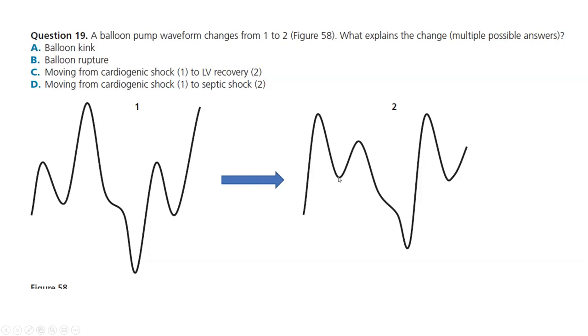Balloon kink and balloon rupture can cause poor augmentation, but they will cause a more alarming change in the helium waveform. The fact that we're not showing a helium waveform here is a hint that this may not be the problem. Another hint is the pulse pressure between the two beats. This is the pulse pressure of a failing heart. It's small, and you're getting a big augmentation. This is a big pulse pressure. It's not a pulse pressure of a failing heart, and maybe that's the problem.